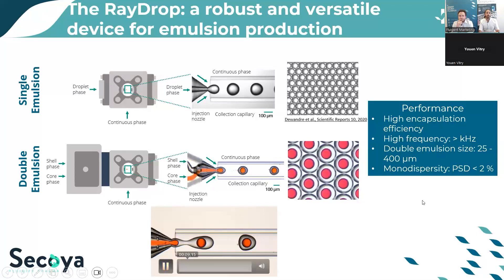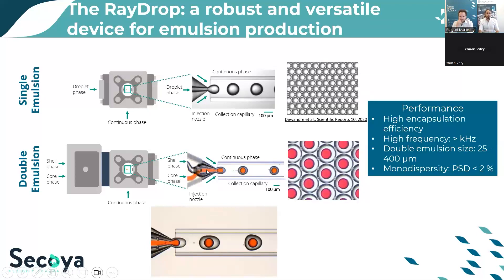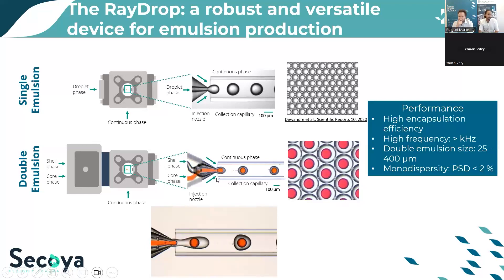With this technique we achieve encapsulation efficiency higher than 95%, since the core phase containing the active ingredient is totally encapsulated inside the double emulsion. We can generate droplets at high frequency up to kilohertz generation rates. Double emulsion size — as well as single emulsion — can range from 25 micrometers up to 400 micrometers with high monodispersity, with a size dispersion lower than 2%.